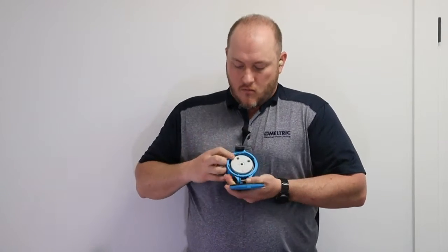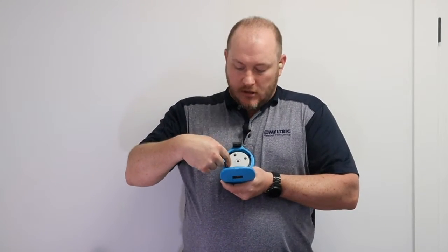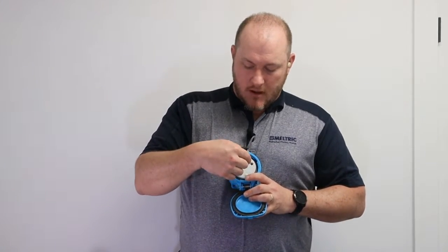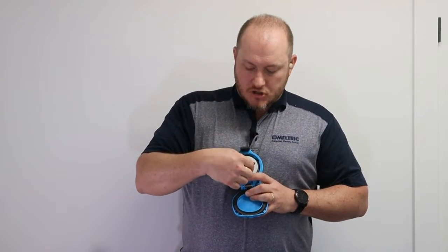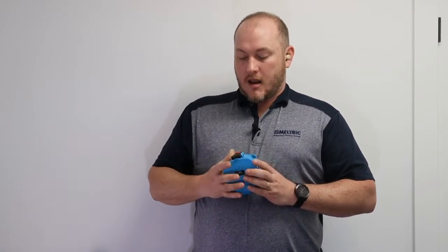When we have a Meltric plug and receptacle, you have this dead front shutter, and therefore there's no ability to get in and do any of that shorting. So this dead front shutter is the key feature of a Meltric device that eliminates that arc flash hazard, because there's no way for you to short in an exposed receptacle, no way to short one pin to another pin. So you can't go phase to phase, you can't go phase to ground, you can't short the devices, and therefore you can't have an arc flash.